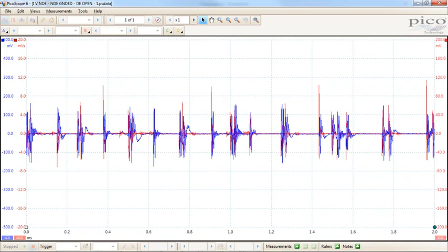30 volts. And here, if you look carefully, you'll see the common mode. You see those raised sections. That's why I was saying I marked how classic your waveforms were, because this is a full installation. And this voltage here is clearly not related to the drive's common mode voltage, because on another set of measurements, when we measured without the fan coupled, it was much lower. So this is induced by the fan, so it's electrostatic, and that's why you get that high voltage. Remember, it's still earthed to some extent. It's not allowed to float completely. So now look at that voltage there.